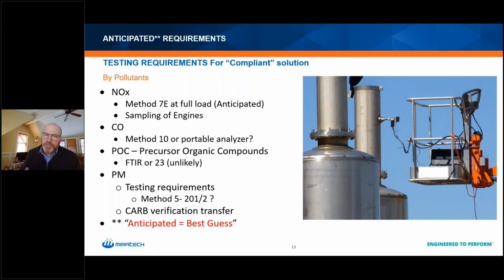I don't think there's going to be any CO analysis that needs to be done. If they ask for something like Method 10, we're going to counter with a proposal to do a portable analyzer. I don't believe there's going to be any POC testing. This is a very expensive test, typically FTIR or Method 23, and we're going to try to avoid that. Because the oxidation catalyst that's part of our system works so incredibly well, the HAP should be down in non-detectable levels, so I don't believe that testing is going to be required there.